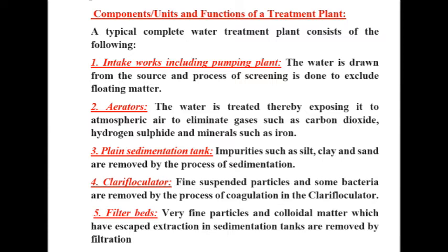Third, plain sedimentation tank. Impurities such as silt, clay and sand are removed by the process of sedimentation. Fourth one is clariflocculator. Fine suspended particles and some bacteria are removed by the process of coagulation in the clariflocculator. Fifth one is filter bed. Very fine particles and colloidal matter which have escaped extraction in the sedimentation tank are removed by filtration.